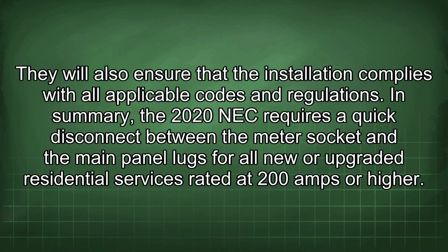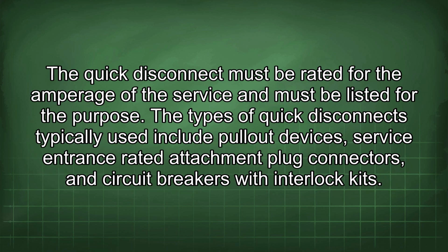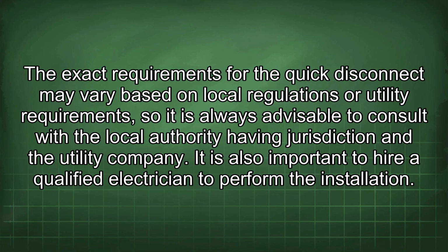In summary, the 2020 NEC requires a quick disconnect between the meter socket and the main panel lugs for all new or upgraded residential services rated at 200 amps or higher. The quick disconnect must be rated for the amperage of the service and must be listed for the purpose. The types of quick disconnects typically used include pull-out devices, service entrance rated attachment plug connectors, and circuit breakers with interlock kits. The exact requirements for the quick disconnect may vary based on local regulations or utility requirements, so it is always advisable to consult with the local authority having jurisdiction and the utility company.